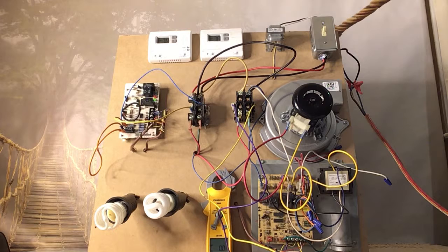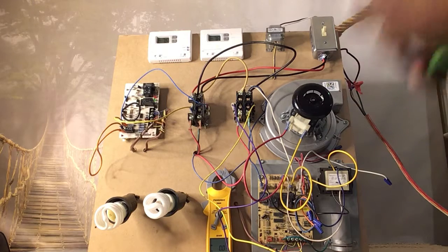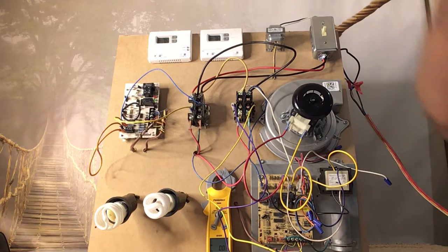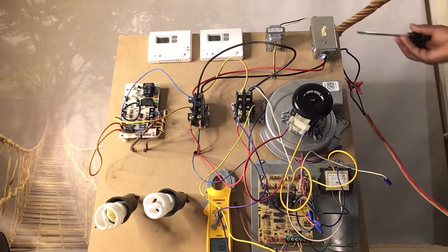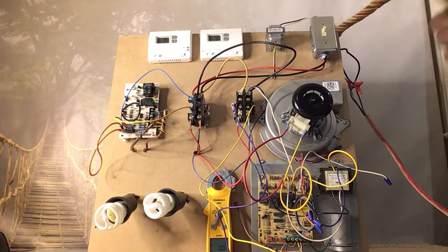You'll go to the thermostat and you'll turn it on to heat or cool. For this particular demonstration, we're going to be doing it in cooling. So just to run through the steps of the sequence of operation and how the unit actually works. So normally what you'll see is a switch or some type of power source, and that power source will lead back to some type of circuit breaker where the power actually originates at. So one, you want to make sure that you got power.